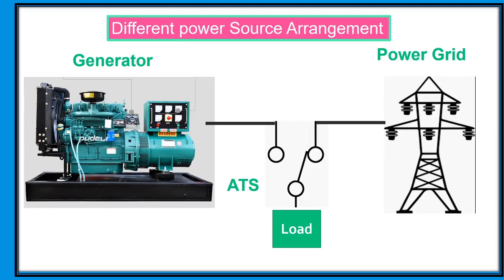There are a variety of arrangements available in utilizing two power sources in automatic transfer switches. The first one is utility grid to generator source. The usual transfer switch arrangement comprises an electrical utility service and a generator for normal and emergency power sources. This system arrangement is typically referred to as an emergency standby generator system.